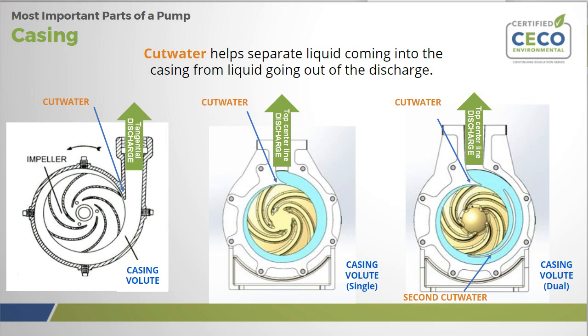Why do people prefer this arrangement more than tangential? It simplifies piping layout. It helps to reduce piping strain because you're actually equally distributing the piping weight to the casing feet. And it makes the casing self-venting, which translates into clear and free passage of air. So that's one key takeaway.